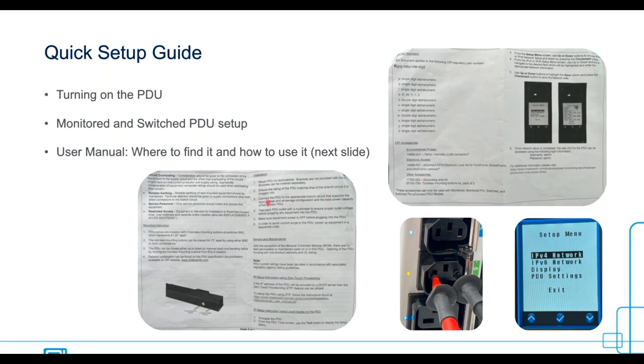The first thing you'll want to do is mount the PDU to the rack or cabinet. Make sure that the rating of the PDU matches that of the branch circuit it's plugged into. Also make sure the PDU is connected to the correct branch circuit that supports the input voltage/amperage and the total power capacity of the PDU. This is a very important step to avoid damage to the unit.